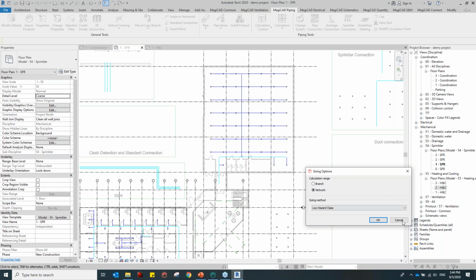You can use the analyze tool to identify the open ends, or use your own ways to find the openings. That can take a lot of time, but you make sure there aren't many openings, only one feed point. From that feed point, it will automatically size, whether it's sprinkler, chill water, cold water, or sanitary pipes. Whenever you do sizing, you should not have more than one open end.